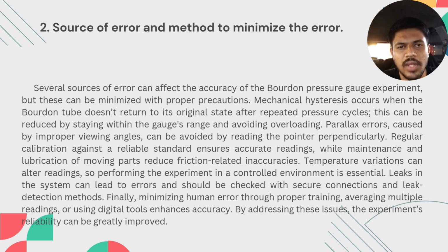For the second question, sources of error and methods to minimize the error. Several sources of error can affect the accuracy of the Bourdon pressure gauge experiment, but these can be minimized with proper precaution. Mechanical hysteresis occurs when the Bourdon tube does not return to its original state after repeated pressure cycles. This can be reduced by staying within the gauge range and avoiding overloads. Parallax error caused by an improper viewing angle can be avoided by reading the pointer perpendicularly. Regular calibration against a reliable standard ensures accurate readings, while maintenance and lubrication of moving parts reduce friction-related inaccuracy.